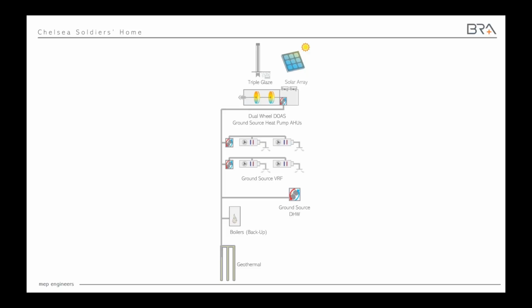And so you can see at the top, we've got our dedicated outdoor air handlers that are providing ventilation. Those have heat pump compressors built into them so that they can heat and cool from that ground loop. At the zone level for each of the spaces, we have water source VRF. And then we also make domestic hot water from our heat pumps to eliminate fossil fuels for domestic hot water. So we'll walk through each of those pieces briefly.